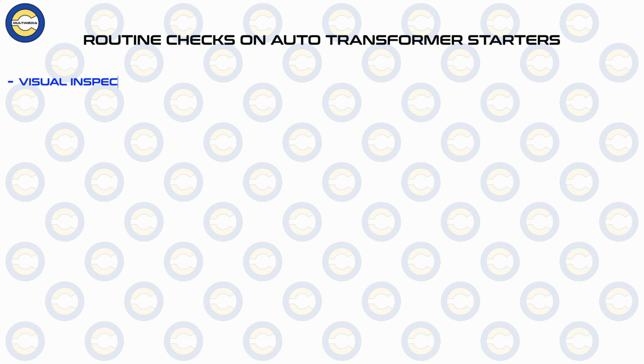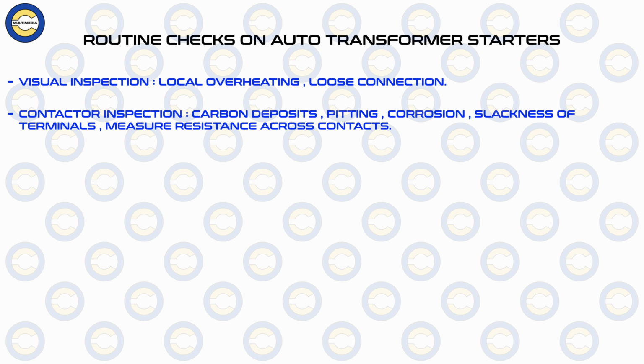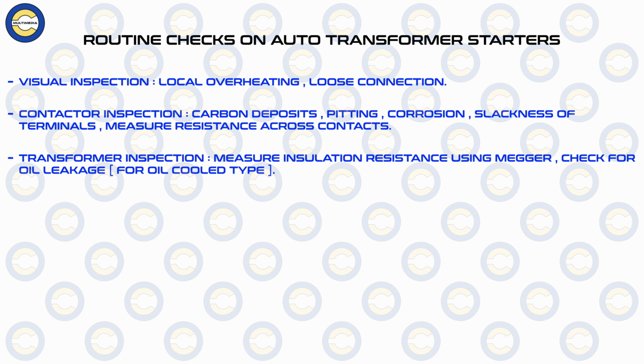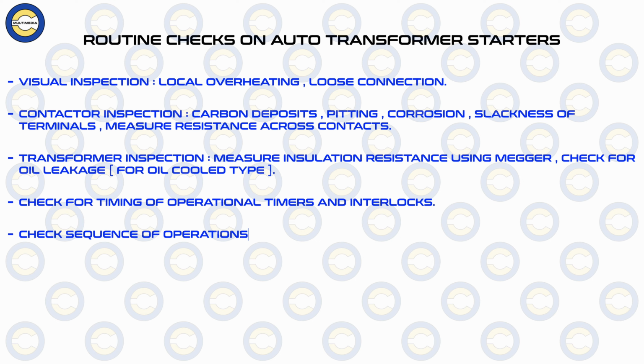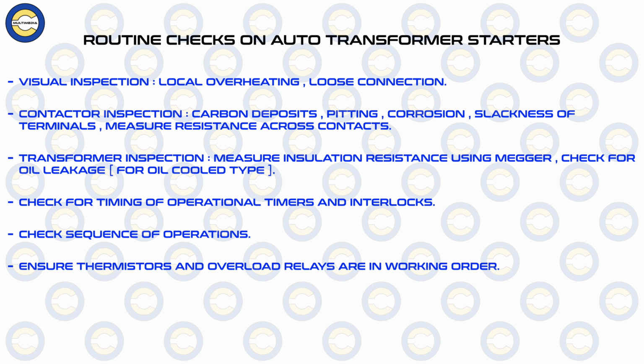So please go through the visual inspections and check for local overheating or loose connections or even carbon deposition on the contacts. In terms of contactor maintenance, we can clean the contact points and check for pitting, corrosion or looseness or slackness. We can also measure the contact resistance. In terms of transformer checks, we can check the insulation resistance using a Megger, check for any oil leakage, but this is only to be done if the design is oil cooled type, and also check that the tap connections are tight and clean. We can check the timing of the operational timers and the relative interlocks, and also check the sequence of operation. And in terms of preemptive checks, we can also check that all the overload relays and the thermistors are in proper working condition and not malfunctioning at any point of time.